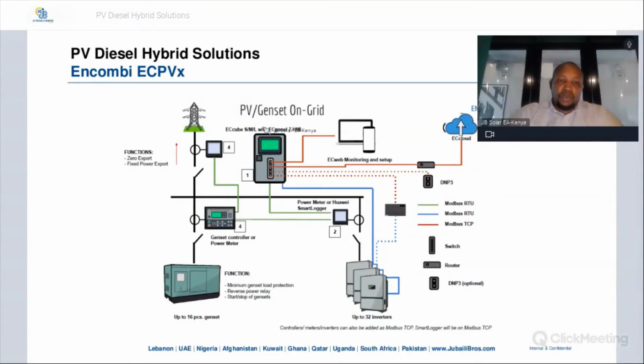And this is how it works with the PV genset when it's on grid. Previously, we did not have the grid integrated into the system, and now we have the grid integrated. Then this is the line diagram when you integrate the grid, the diesel generator, as well as the PV array.